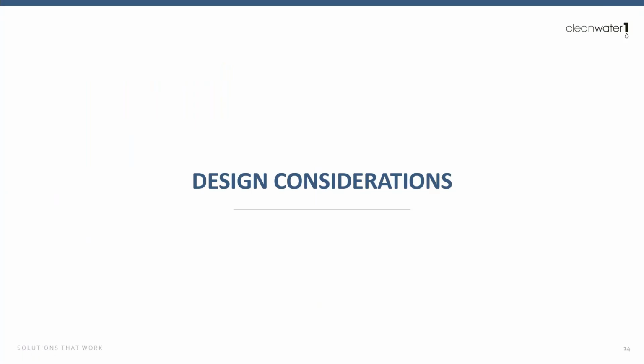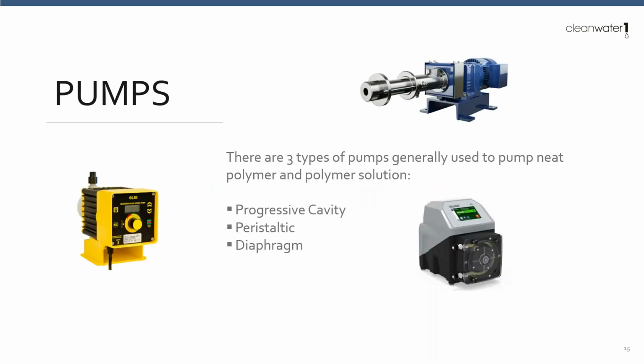So when we're looking at polymer systems, we looked at the sizing, but now we want to look at different design considerations as far as what pieces of equipment we are using to build these skids. One of the big ones is pumps, right? So all of these skids, whether it's an emulsion polymer system or a dry polymer system, somewhere in the process it's going to have pumps. Neat polymer pumps and solution metering pumps are generally going to be between 3 types of pumps, which is progressive cavity, peristaltic, and diaphragm.